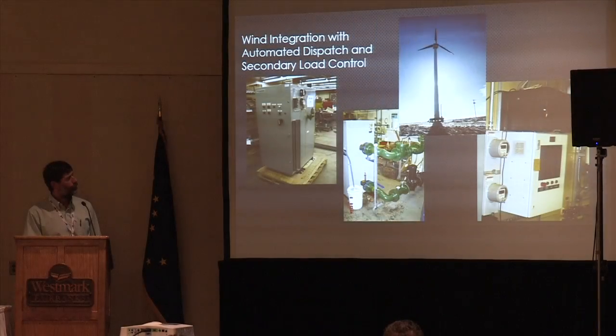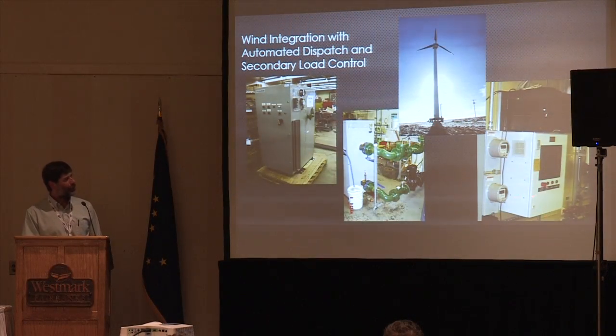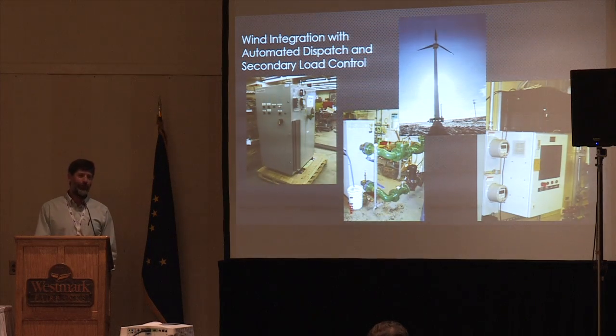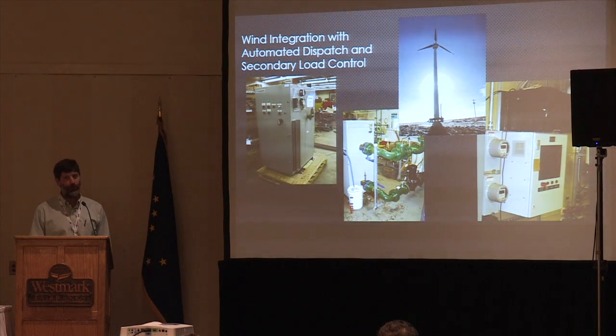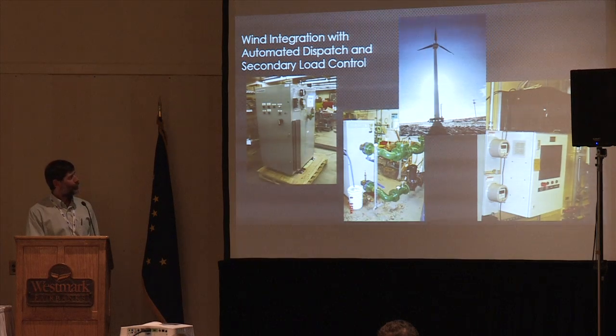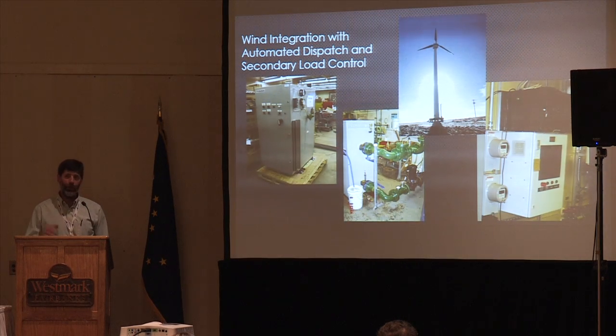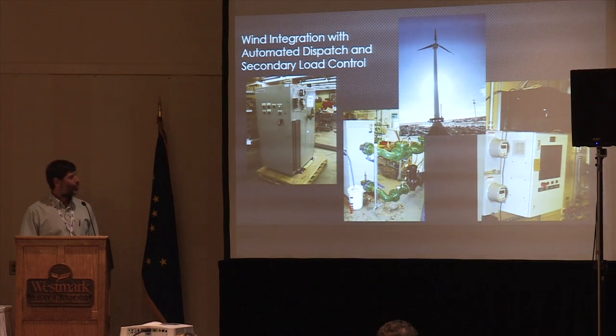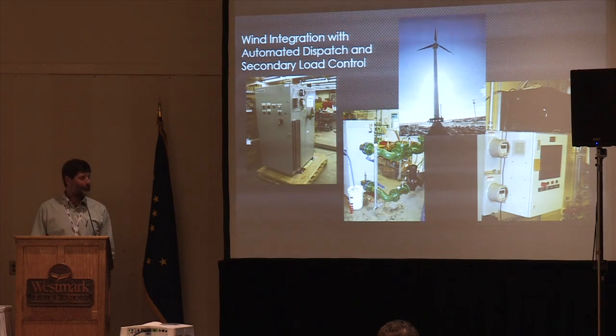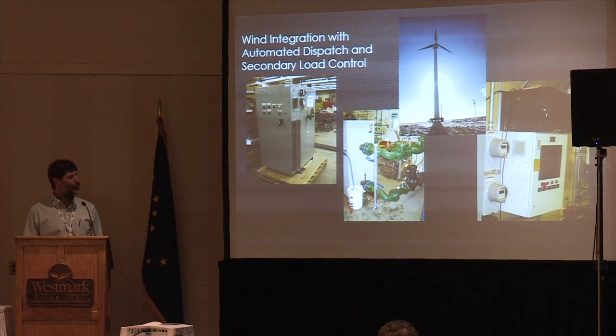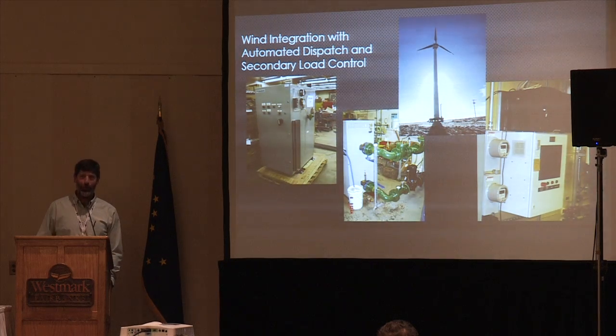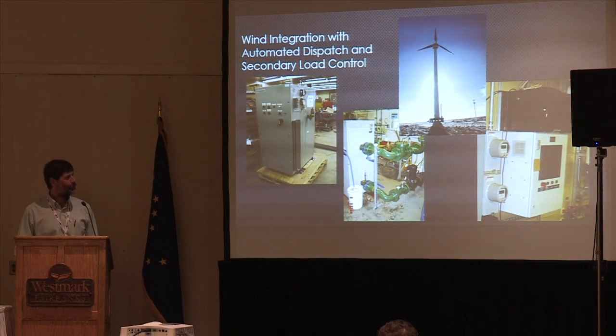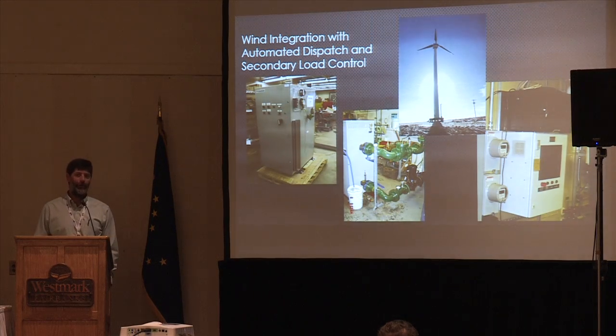There's a wind dispatch panel which looks at the loads of the village, which engines are online, and tells how many wind turbines can run. The dispatch control also tells the boiler which elements to fire, all those sorts of things. It's more and more becoming a computer technology world, whereas, as other speakers have said, back in 2000, 14 years ago, it was fuel, air, diesel, make it run, and that's about all you needed to know.